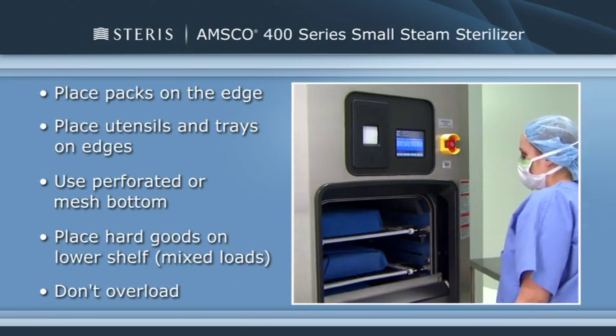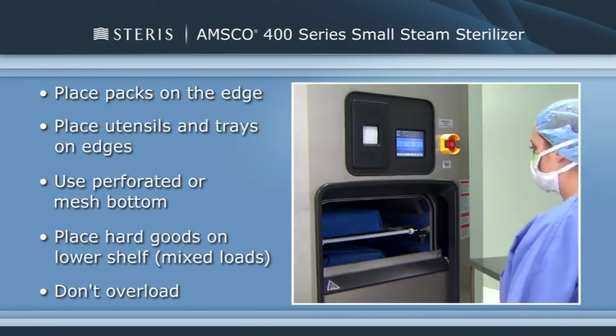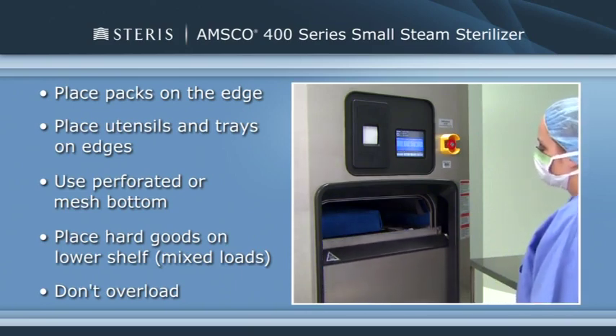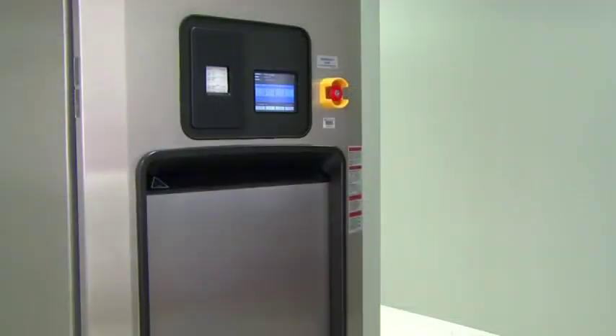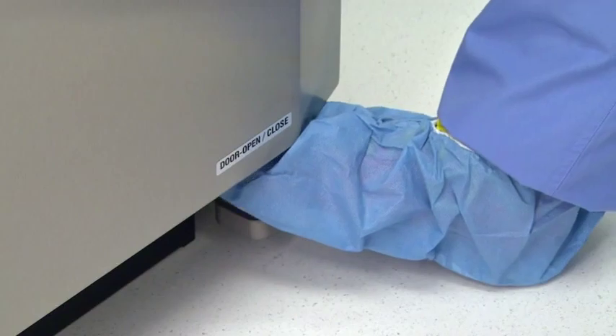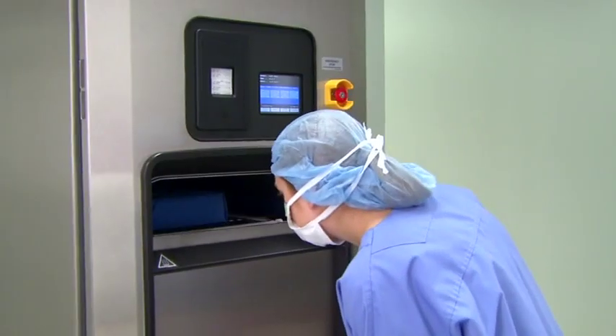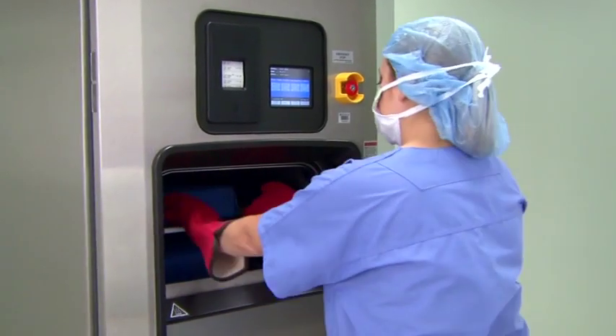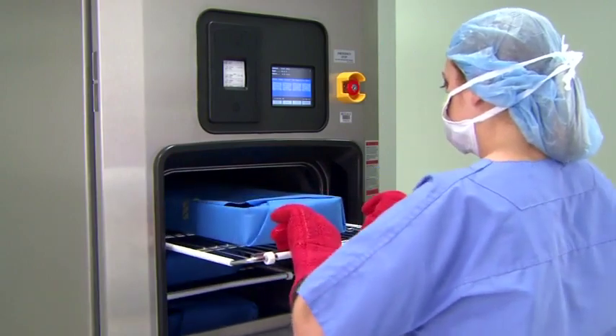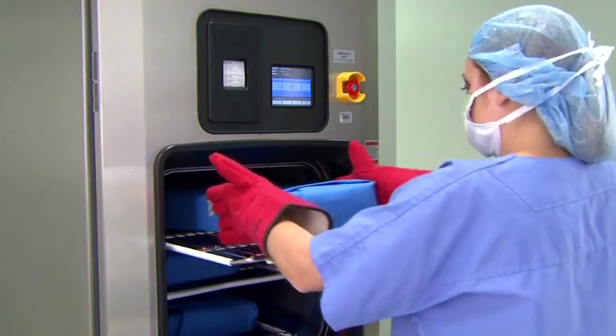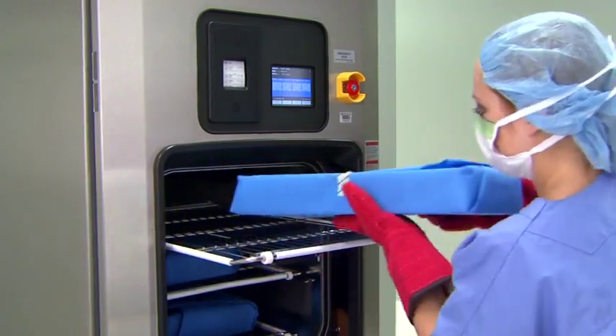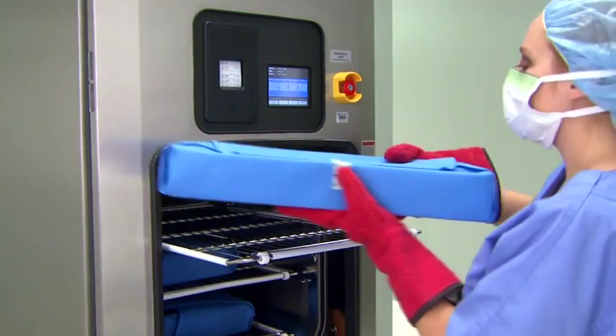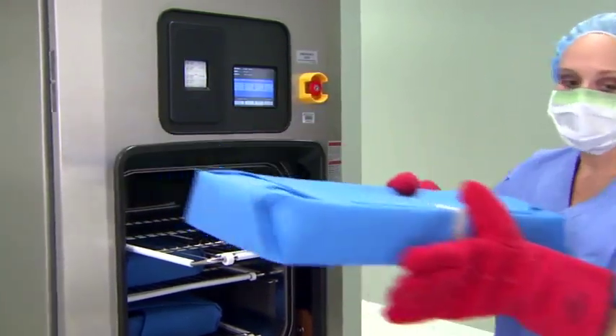After placing the load in the chamber, close the chamber door. The sterilizer is now ready to run a cycle. At the end of a cycle, when the end of cycle tone sounds, open the chamber door. Wear clean gloves and use clean towels or mitts as pot holders to carefully remove the load and avoid unnecessary handling. Never place a sterilized tray on a solid shelf or cold surface. Once it's cooled, place it on a wire shelf.